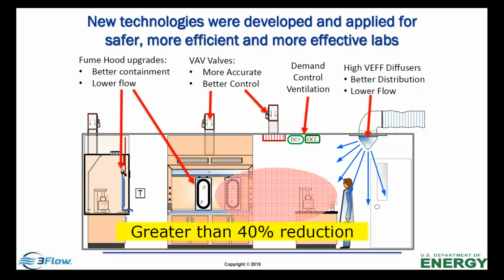So they gave us a grant and they let us do a study, and we determined what all the really good characteristics of the high performance hoods were, and we came up with our first iteration of a retrofit kit. And this retrofit kit goes into existing hoods, and it basically allows the hood to reduce its exhaust by 35 to 40%. And with having sliding shields on the front, you can now have whatever face velocity you want, from 100 feet down to 60, and still have the hood reduce its exhaust by 35 to 40%. Out in the state of California, for instance, the OSHA requirement is for 100 feet per minute face velocity. So this is becoming a big deal at UCI and in the campus system and through the state of California, to have the ability to maintain 100 feet per minute face velocity.